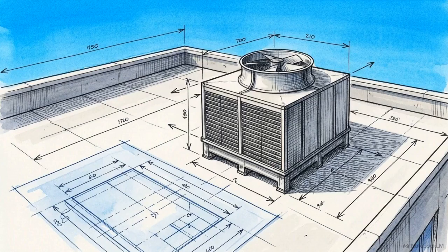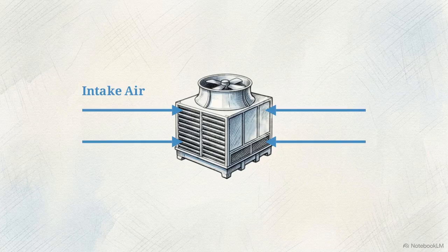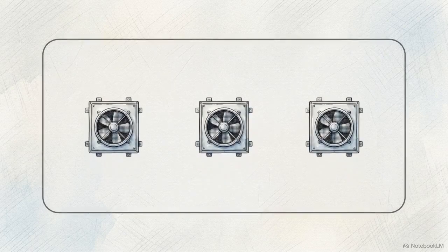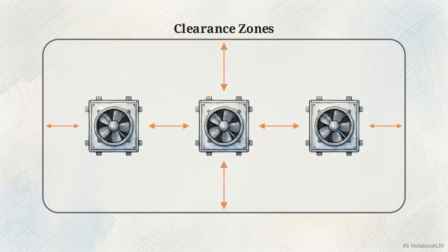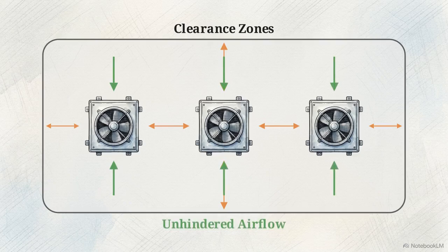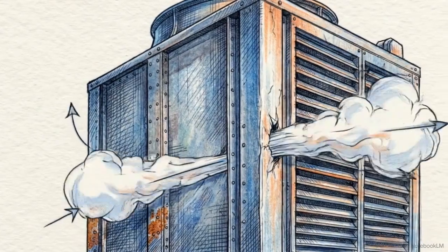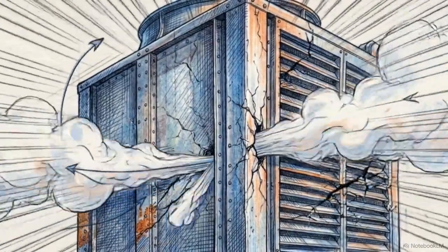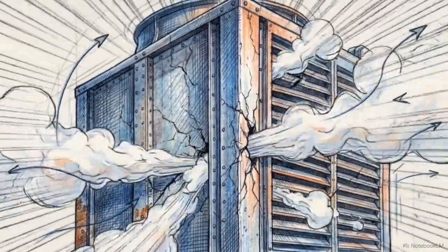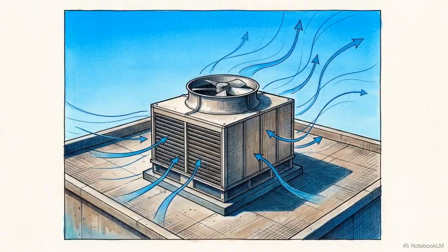Step 1 is positioning. You need to place the unit in an open space, which is typically a rooftop terrace. The system fans are designed to draw air in, but they have to overcome a baseline static pressure to function. This top-down diagram shows exactly why spacing matters. You have to maintain strict, measurable distance from louvers and surrounding walls, as well as any adjacent cooling towers. If you starve the unit of this intake air, the condenser loop cannot reject its heat, causing the whole process to stall. Proper placement ensures you are securing the actual volumetric airflow required to keep your chillers alive.